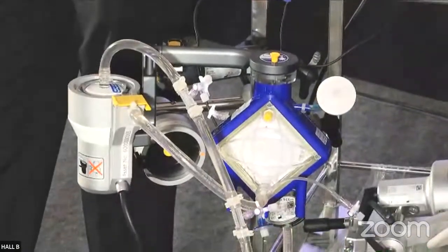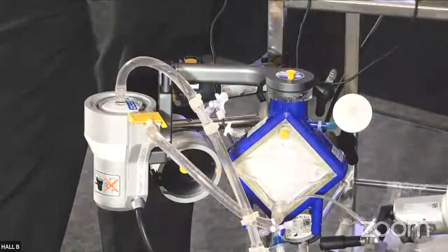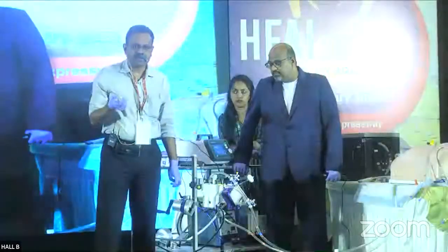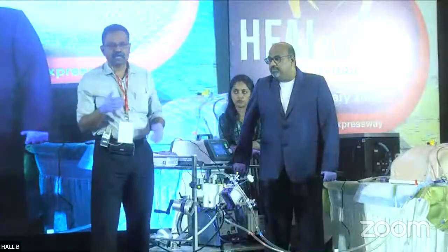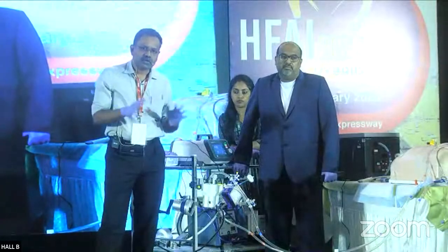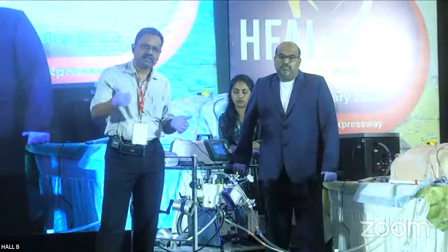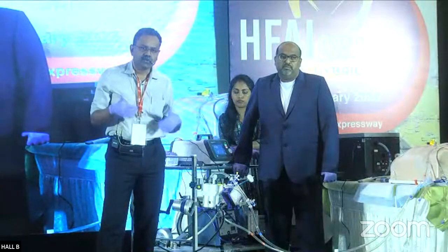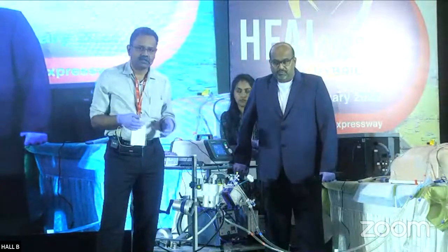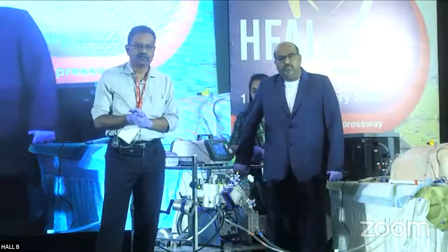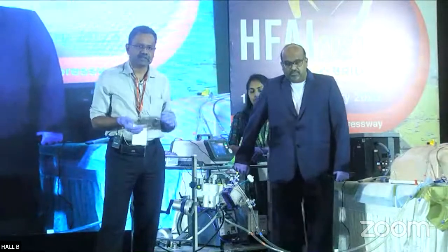The difference between P2 and P3 should be around 30 or so. That is more important. Generally, if any isolated P2 or P3 goes more than 300, the chance of a blowout is very high, where the tubing connection is, that can come out. So it is always better to keep the pressures less than 300 mmHg. The more the pressure, the tube can get disconnected. So that's why we are monitoring these pressures.